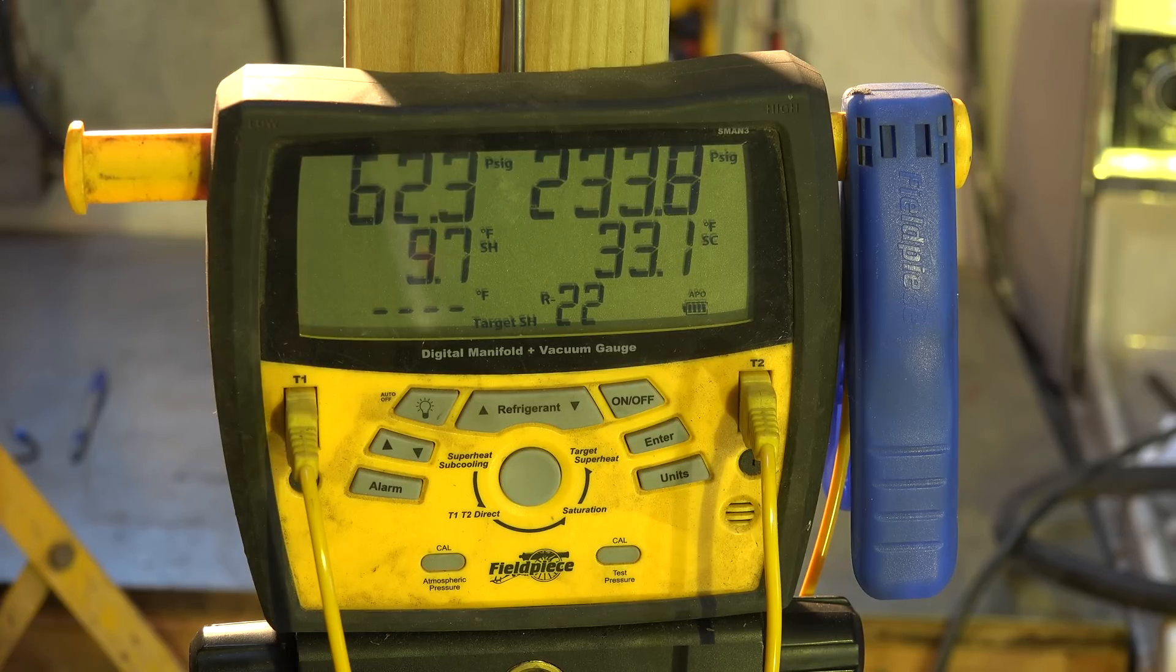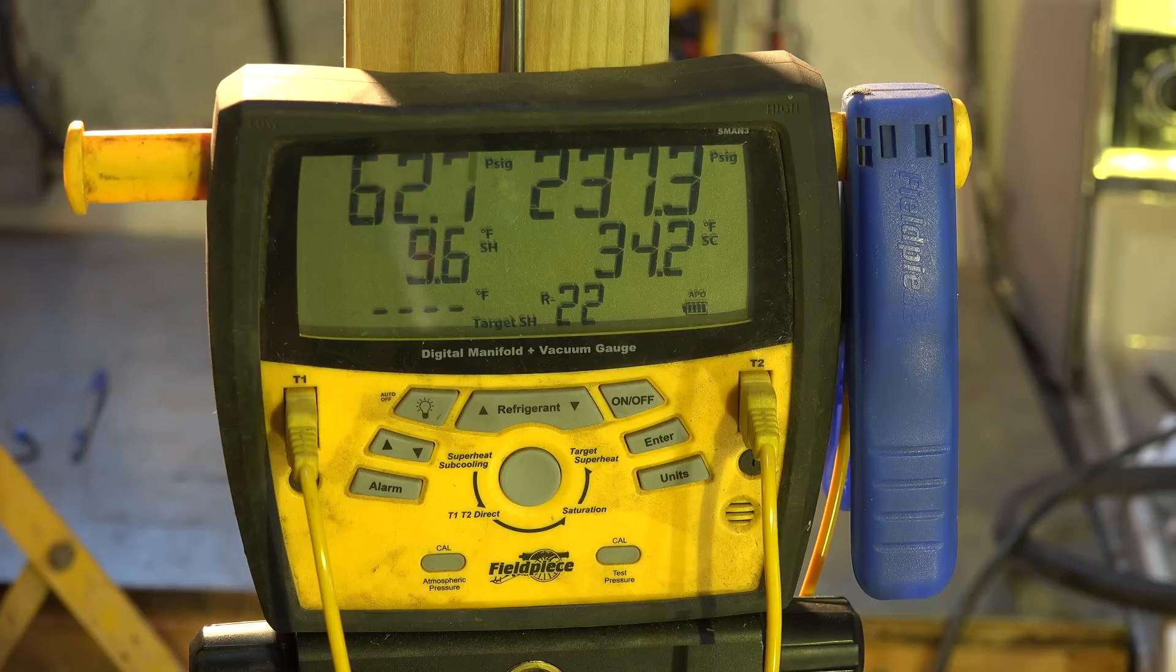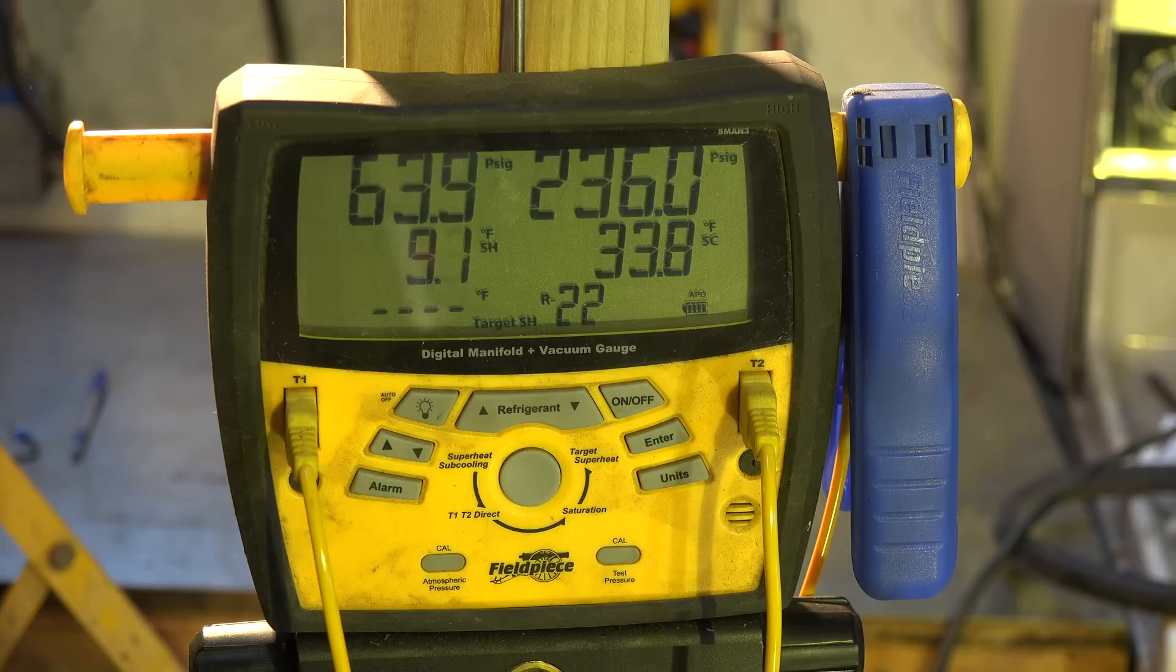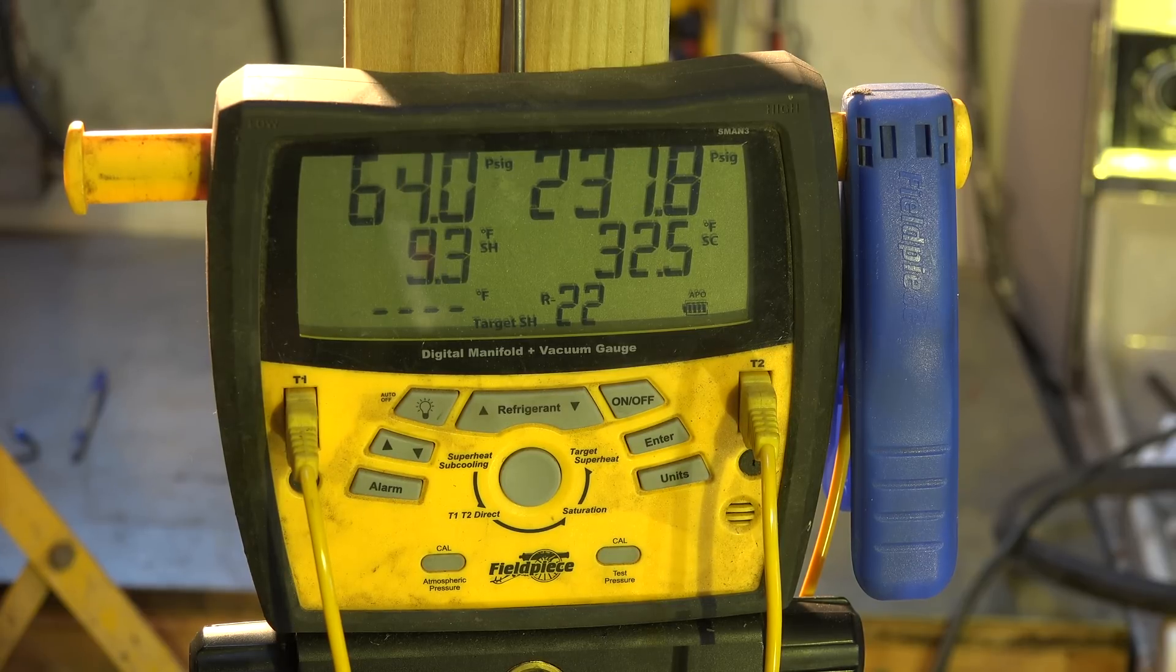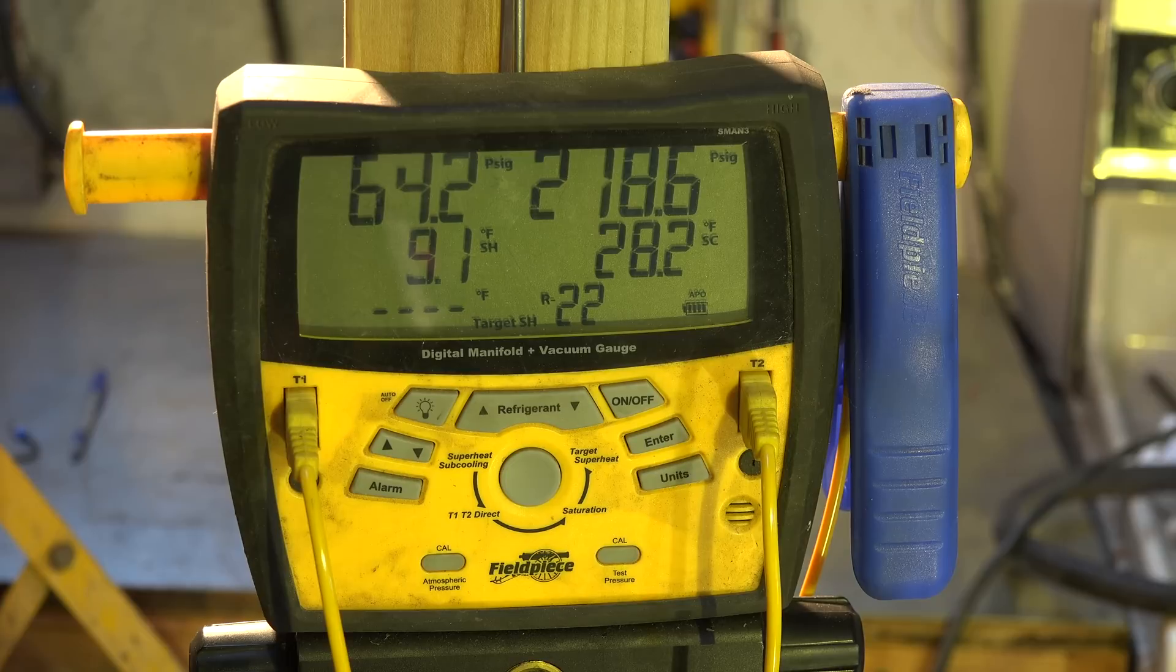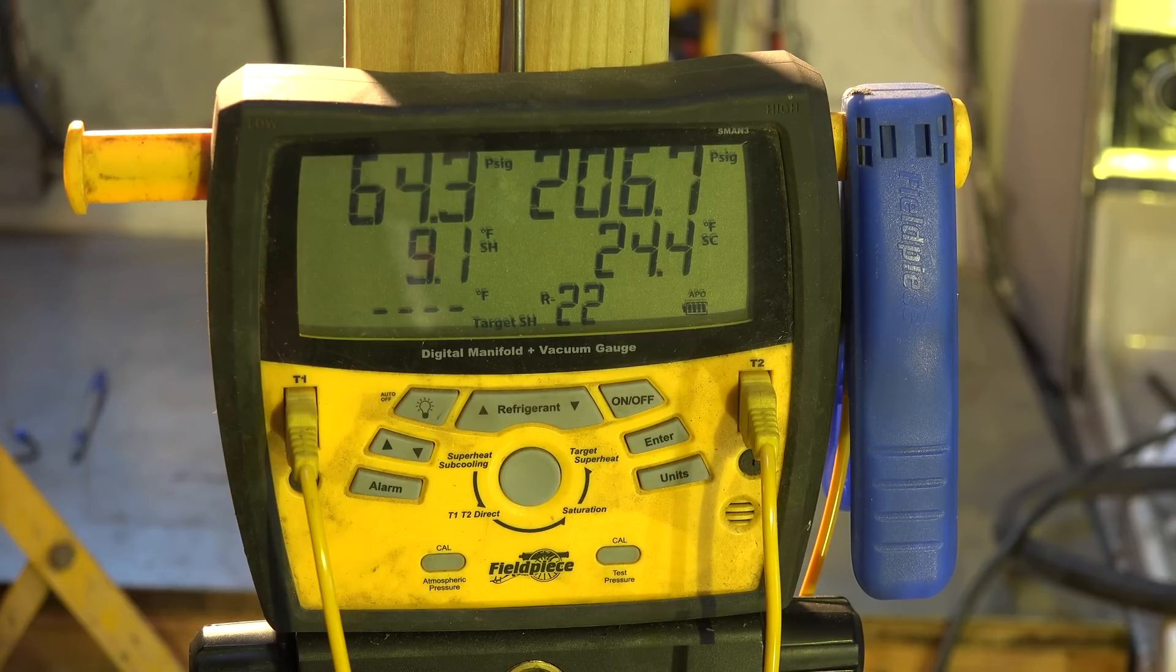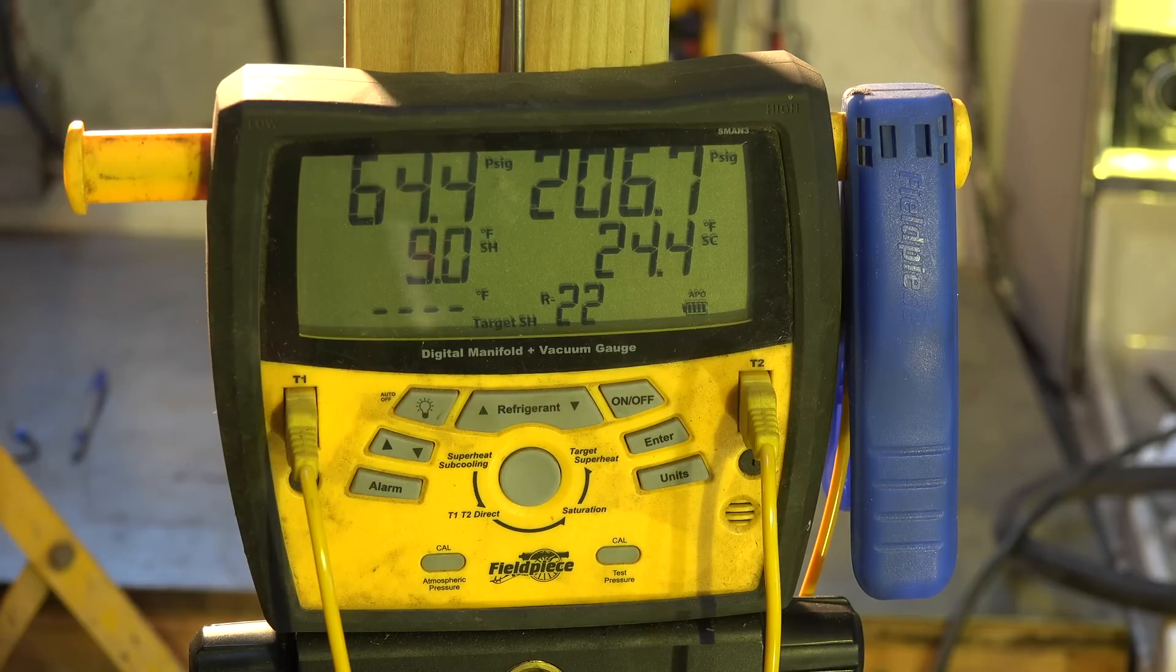Head pressure is going to start the fan pretty soon. It gets to about 235 and starts. Okay, it's coming down because the fan's on. Now it's going to have some lag here because that higher head pressure is going to continue to push refrigerant through for a while and the subcooling is going to continue to go down.